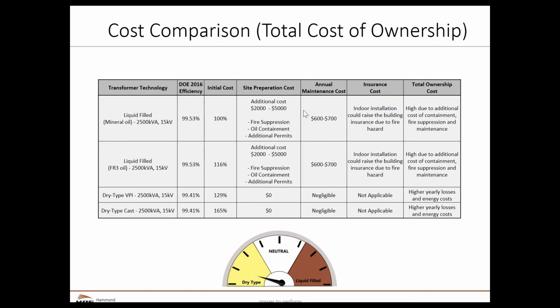So the initial cost for dry type tends to be more for the actual transformer. However, site preparation for liquid filled tends to be quite a bit more. And if we have to do fire suppression, oil containment, additional permits, if I had to build a vault type room, the cost that we have here for site preparation could be even several times what we have listed here. So one of the things, again, when somebody is installing or has specified a liquid transformer and now they want a dry type equivalent, there isn't a dry type equivalent. There's a whole bunch of stuff that has to be redone, and we'll go into the specifications later.